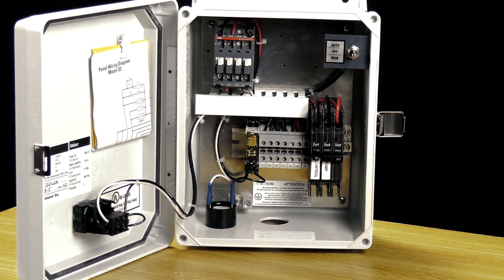Of course, there's a big benefit with operating the controls on a dedicated circuit, because in the event that you have pump failure that results in this breaker tripping, or potentially tripping back to the main breaker that the pump is on, you wouldn't be notified of an alarm condition. So having that on its own breaker, or its own dedicated circuit, is going to be advantageous to the reliability of the application.